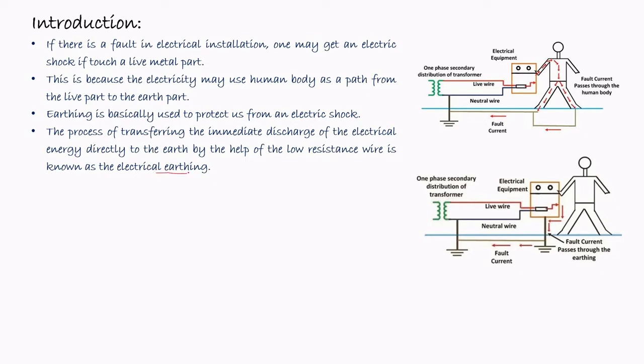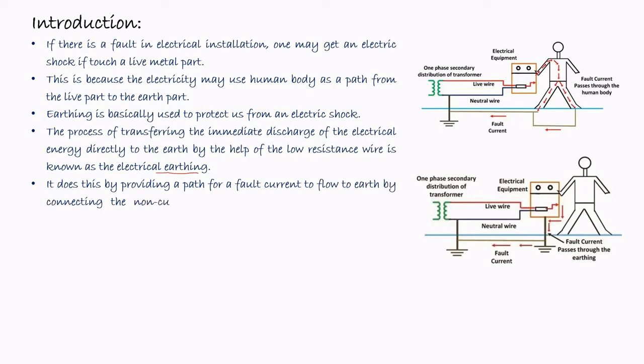So basically the concept of electrical earthing is that any equipment or the supply system should be connected to the earth by using a very low resistance wire, so that if there is any fault, the electrical accident can be avoided. It does this by providing a path for a fault current to flow to the earth by connecting the non current carrying part of the equipment or neutral of the supply system to the ground.